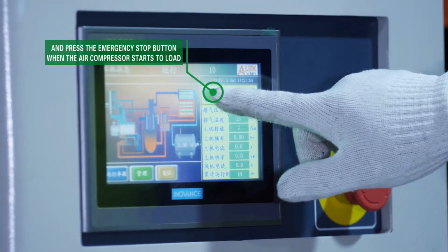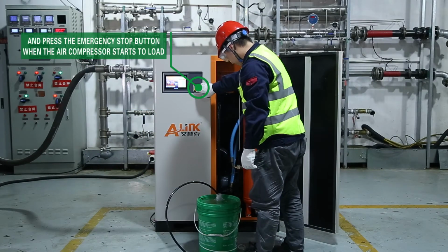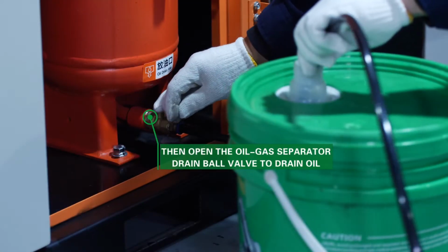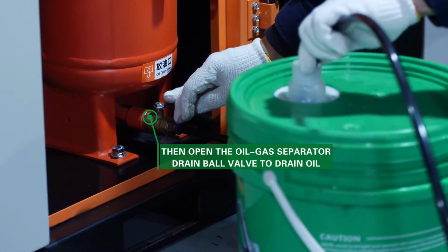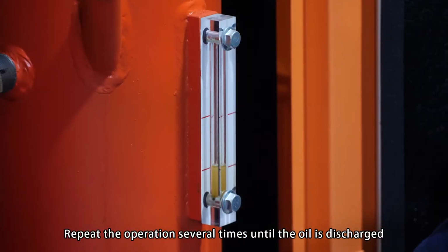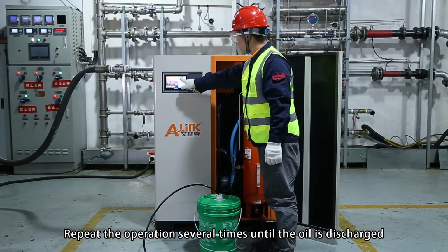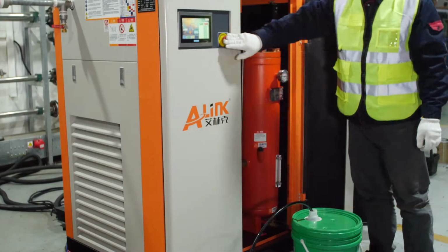Start the air compressor and press the emergency stop button when the air compressor starts to load. Then open the oil-gas separator drain ball valve to drain oil. Repeat the operation several times until the oil is discharged.